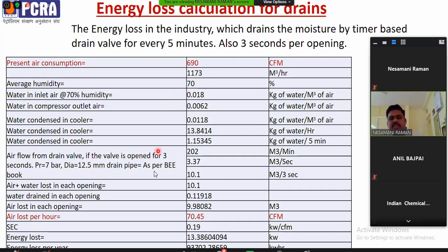At 7 bar, what will be the air flow? I calculated using the BEE book. If you calculate everything, as per the specific energy consumption of the compressor, we lose almost 70 CFM of air with the moisture every hour because of the drain valves. That comes to almost 6 lakh rupees of loss per year. Almost 93,000 units will be lost because of the opening.